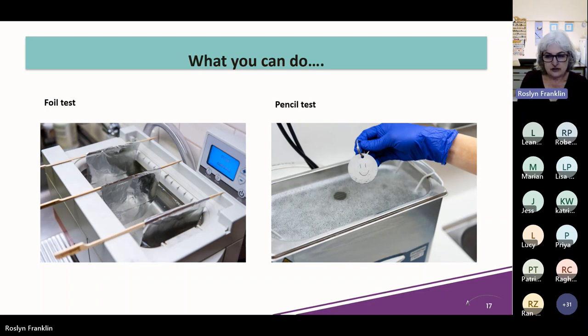Just a note with the alfoil test: tiny bits and pieces of foil will be left in that tank because it's made little holes, and you don't want those tiny bits sticking to any of your instruments. So once you've done this alfoil test, you really should empty the tank, clean it out, refill it.